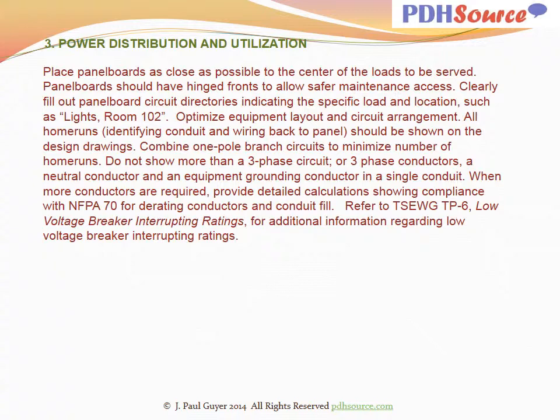Do not show more than a three-phase circuit or three-phase conductors, a neutral conductor, and an equipment grounding conductor in a single conduit. When more conductors are required, provide detailed calculations showing compliance with NFPA 70 for derating conductors and conduit fill. Refer to TSEWG TP6 low voltage breaker interrupting ratings for additional information regarding low voltage breaker interrupting ratings.